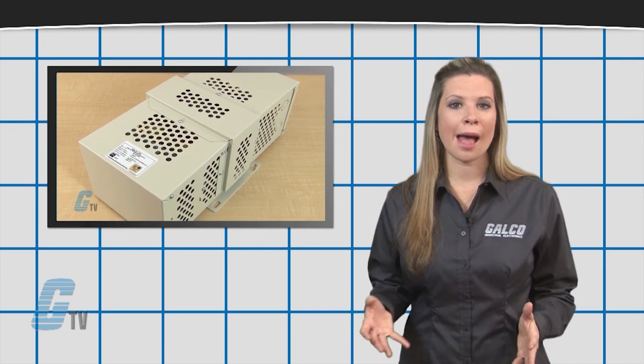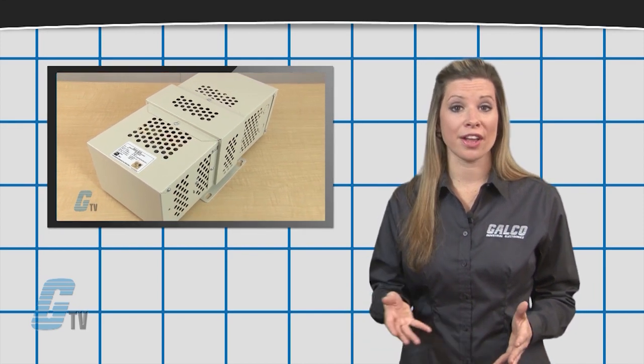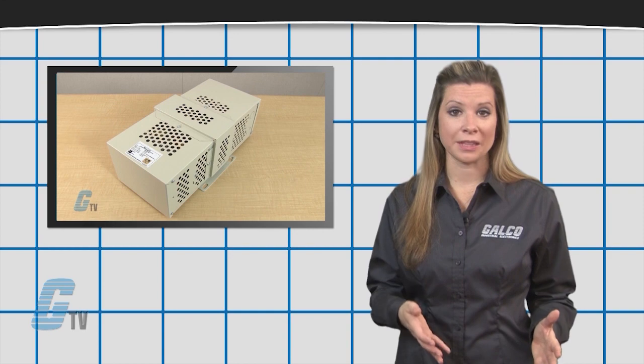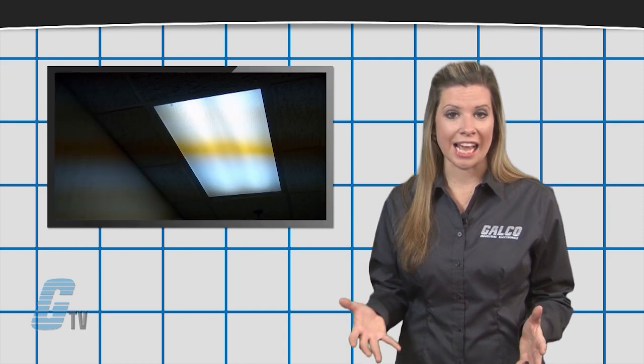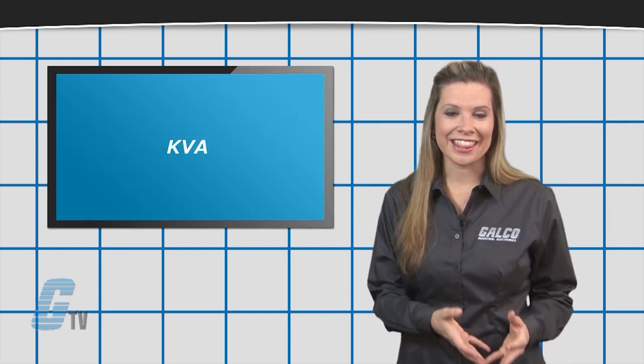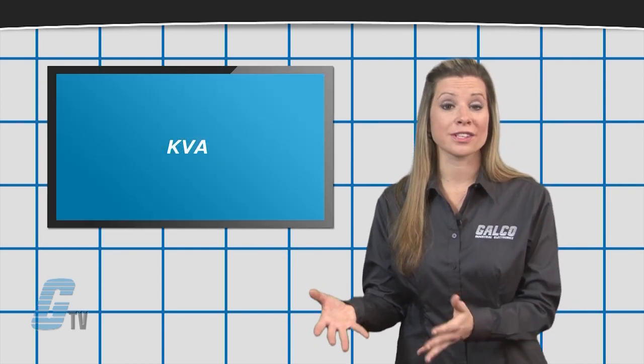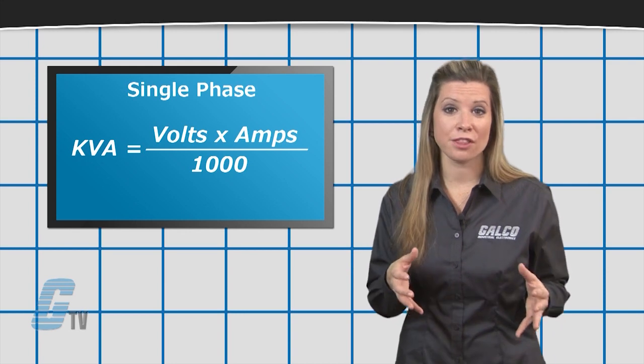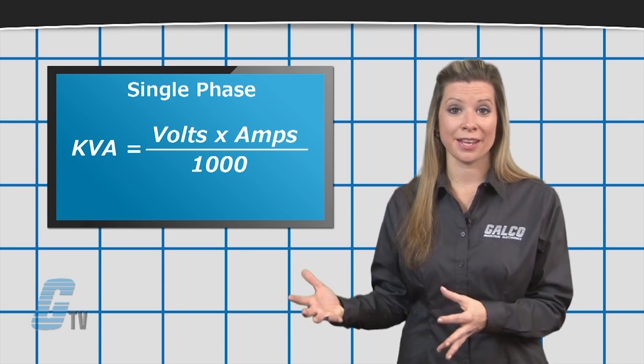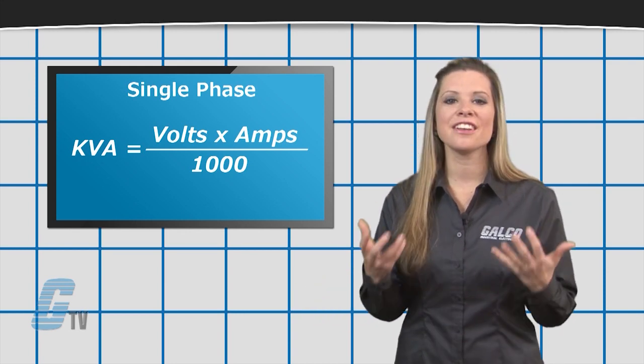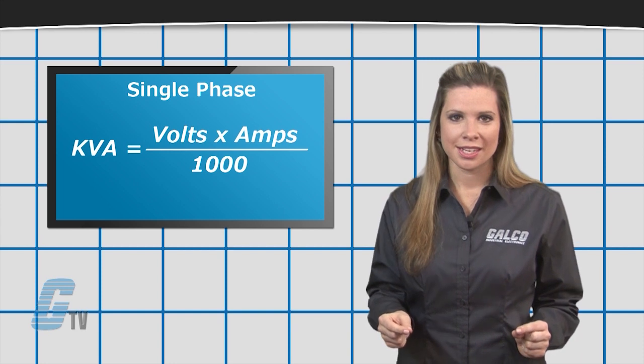This includes a combination of all the various loads that the transformer supplies, including lights, heaters, and motors. To find the KVA for single phase, I can multiply the volts and amperes of the load together, and then divide it by 1000.